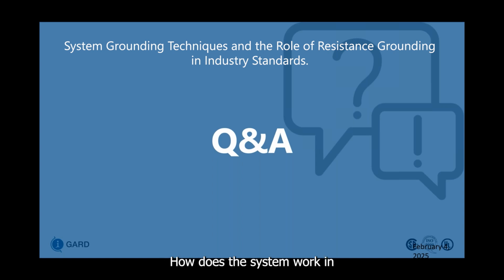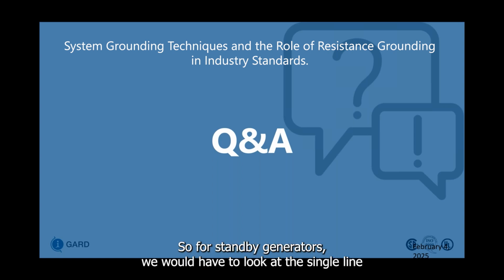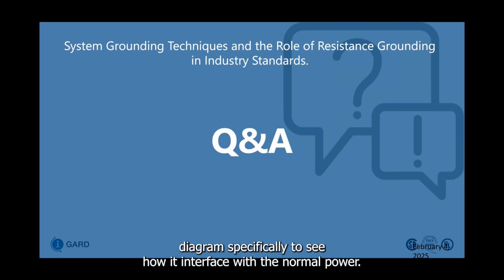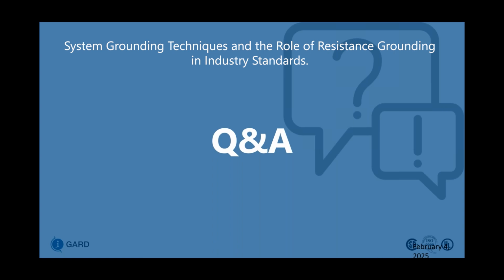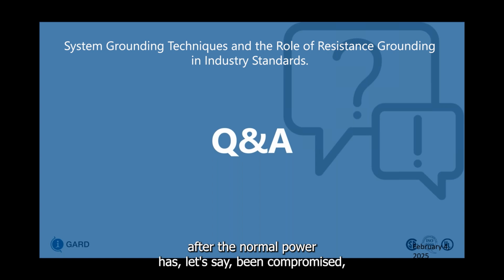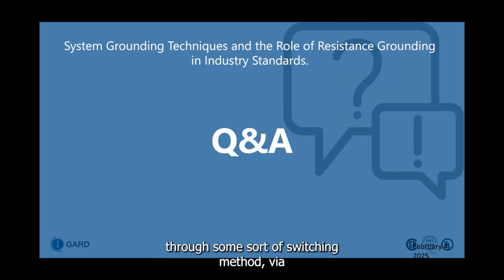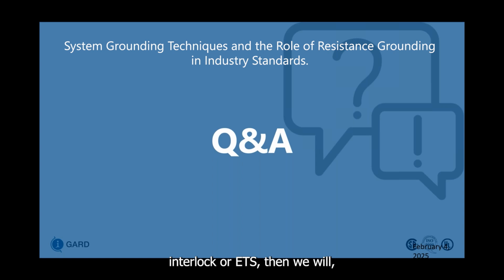How does the system work in power systems with a standby generator? So for standby generators, we would have to look at the single line diagram specifically to see how it interfaces with the normal power. If that standby generator is simply kicking in after the normal power has, let's say, been compromised, through some sort of switching method via Kirk key interlock or ATS, then we will basically apply a neutral grounding resistor as well to that standby generator if the normal power also has a neutral grounding resistor.